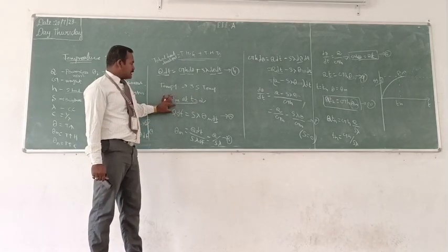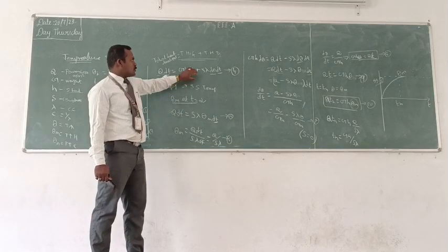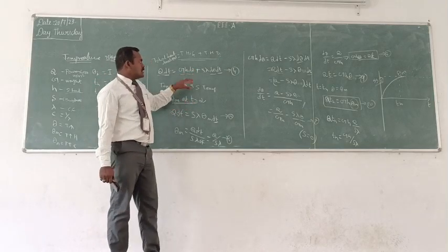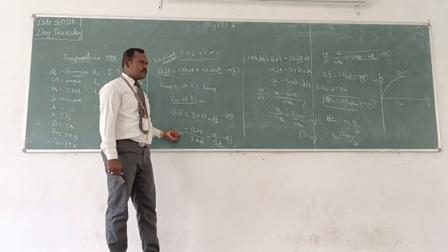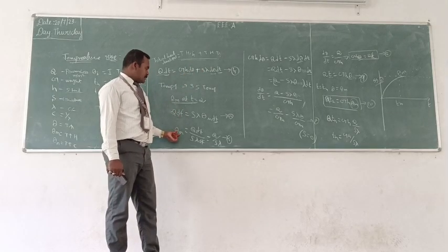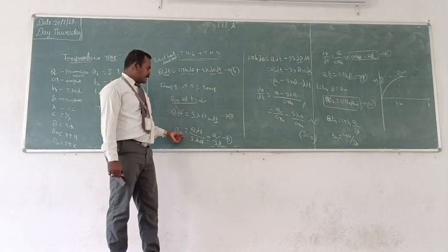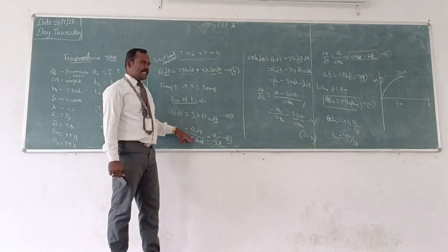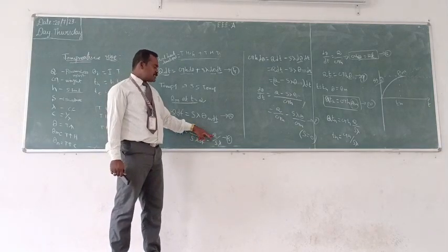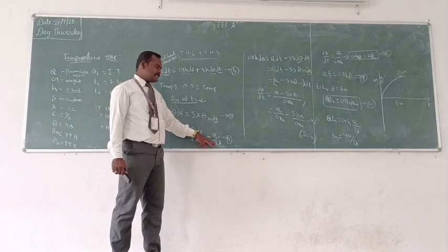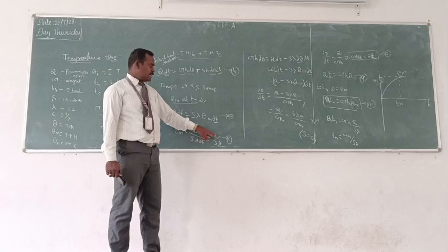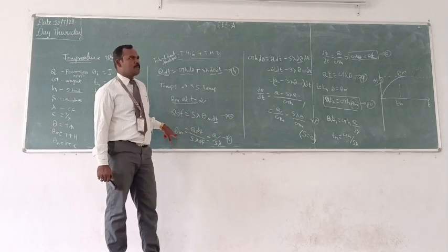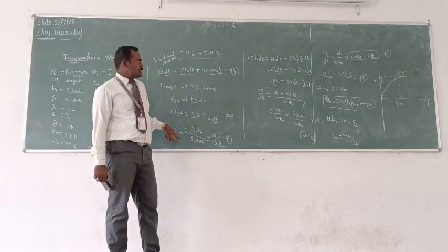Okay, so we can rearrange this expression. Once the maximum temperature rise is reached, we consider only this expression, and from that we can find the maximum temperature rise. It should be theta m equal to Q divided by S lambda, where Q is the total heat, S is the cooling surface, and lambda is the cooling coefficient. So we obtain equation 6, the maximum steady state operating temperature.